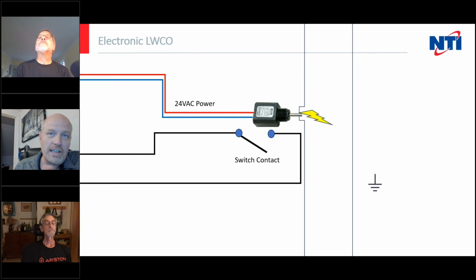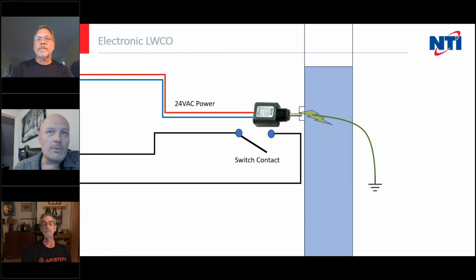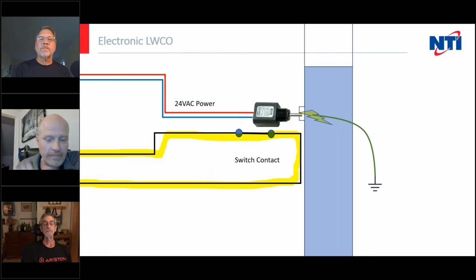And the way these work is the probe that sticks out into the water is charged. It's got an electrical charge to it. And when you add water to the system, that electrical charge gets grounded out to the piping. When the low water cutoff sees that the probe is shorted out to ground, it closes the contact and our safety circuit works. And that's why every 5 years we require that you take this thing out and clean this probe.